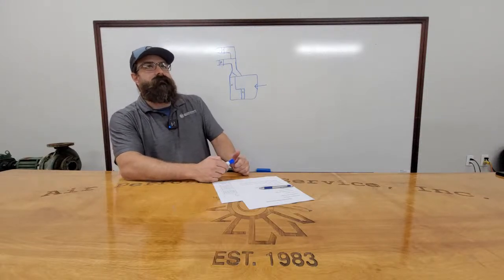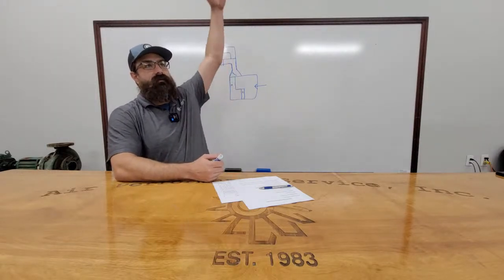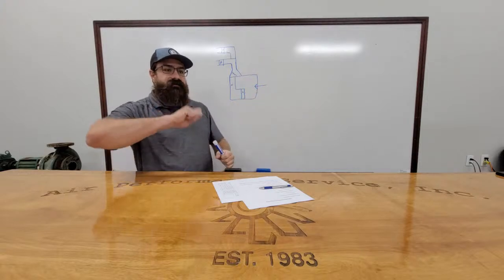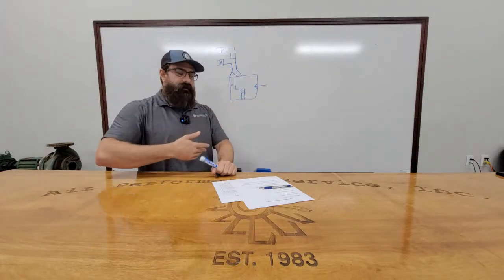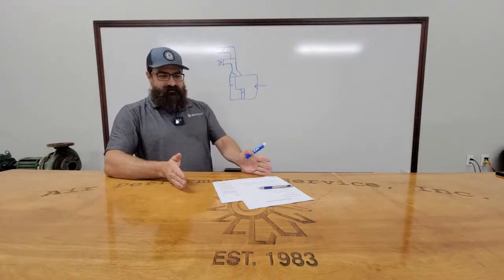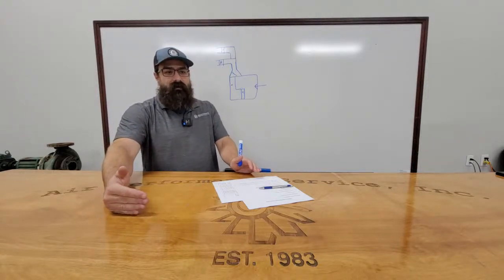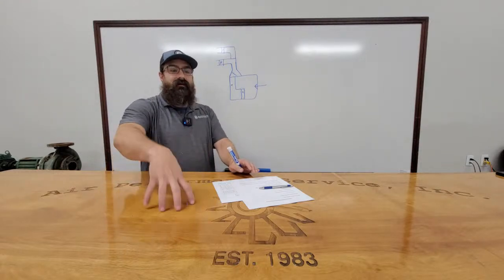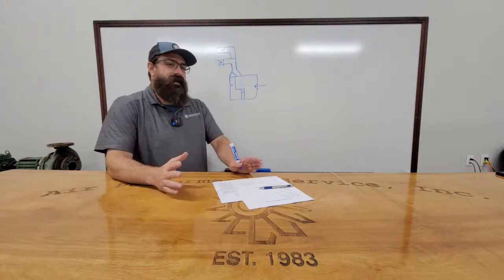And we get that too, but a lot of times what you would have is a makeup air unit that's supplying air down a trunk line into each mechanical room. And then those are set usually with a damper to a certain value. Like, let's just say you've got a 20,000 CFM air handler and you want 10% outside air all the time, right? So you can get some free cooling when that air is colder, kind of like I was saying with the scud and the big VAV box, same type setup.